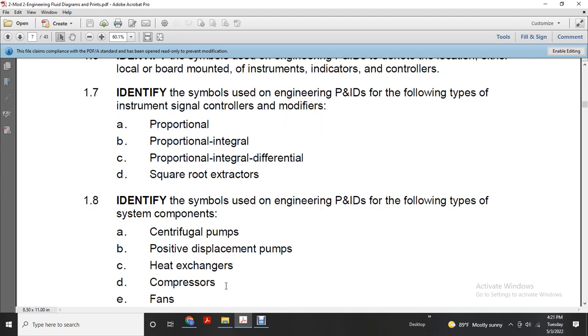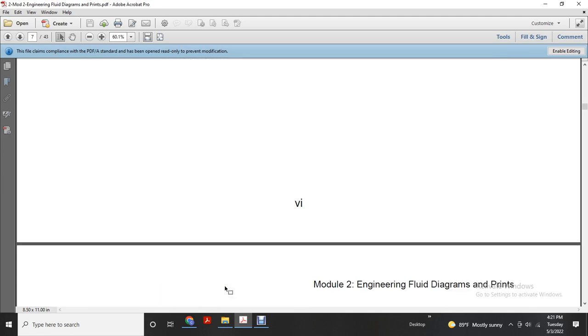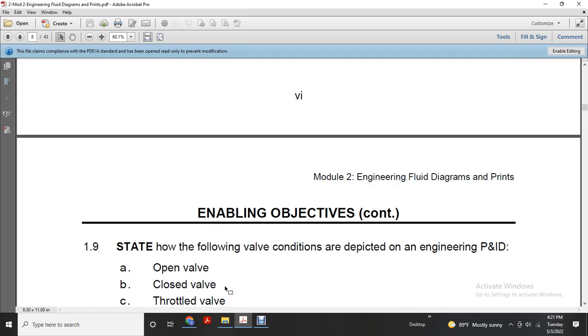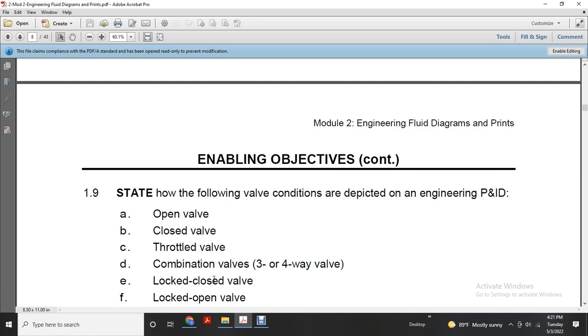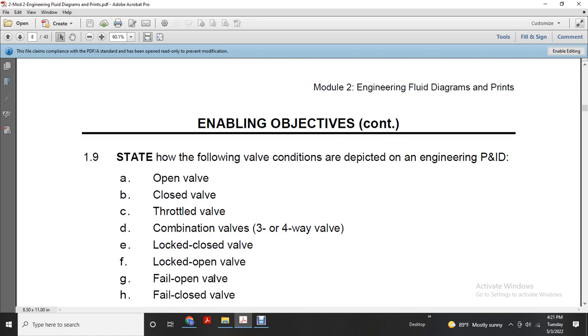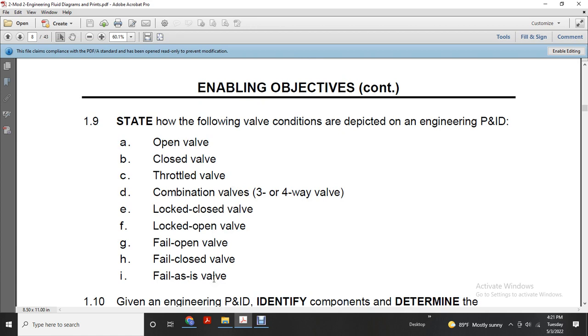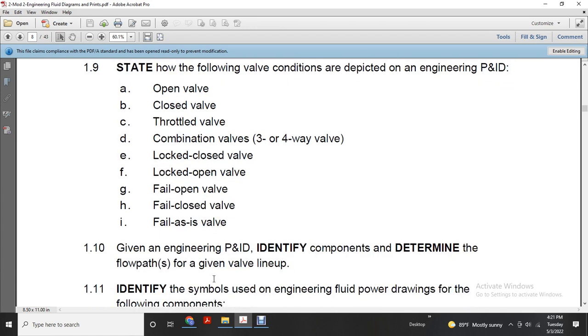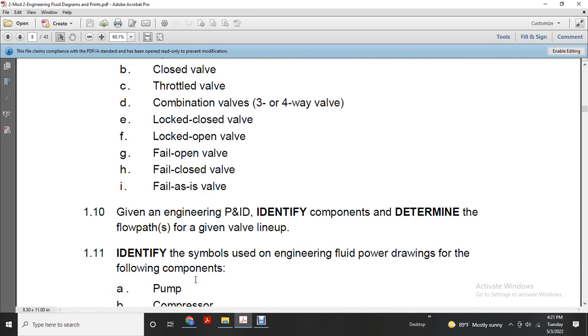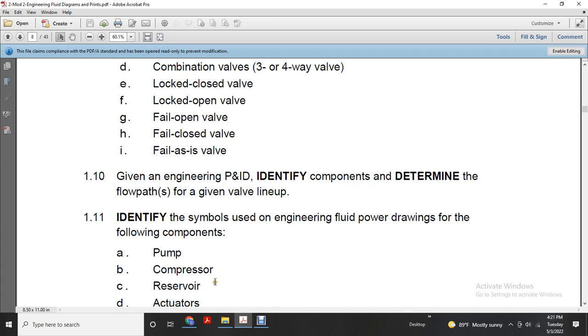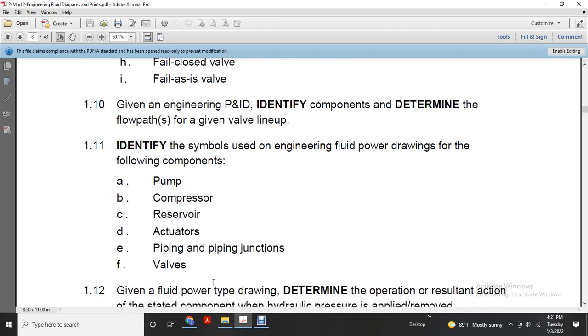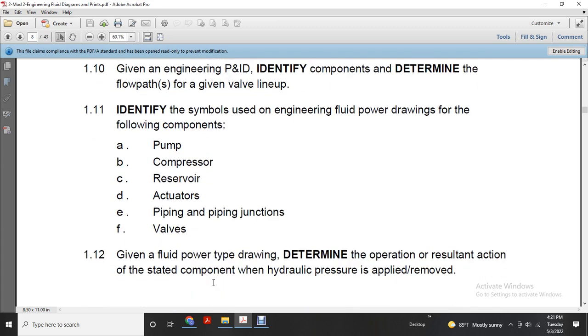components: centrifugal pump, pipe, displacement pumps, heat exchanger, compressor, fans, tanks, filters, strainers. Identify how the following valve conditions are depicted on the engineering P and ID: open valve, closed valve, throttle valve, combination valve, three or four-way valve, locked closed valve, locked open valve, fail closed valve, fail as is valve. Given an engineering P and ID, identify the components determining the flow path, given the valve lineup, and identify the symbols. Given the engineering fluid power diagrams for the following components: pump, compressor, reservoir, actuator, piping junctions, valves, and given a fluid power type of drawing, determine the operation resulting in action of a stated component with hydraulic pressure supplied or removed.